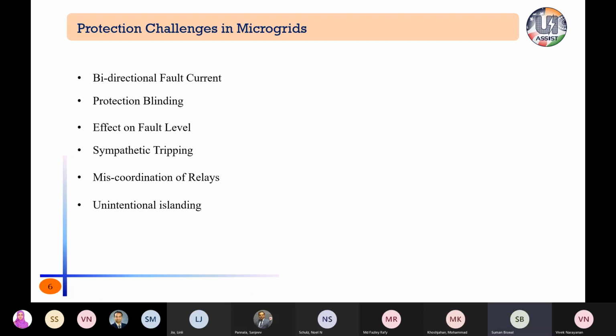And also miscoordination of relays. Relay particular settings, especially time multiplier setting or plug setting, will not cover all the network topologies. For example, microgrids can operate in grid connected or islanded mode, and there may also be many contingency issues as well, for example line outage or DG outage. So a single setting will not take care of the protection issue. This miscoordination of relays happens due to the integration of DGs, or in microgrids these challenges come up. And unintentional islanding of DGs also happens because under a faulty situation, the DG may completely isolate if it exceeds the pickup setting of the relay nearest to it.